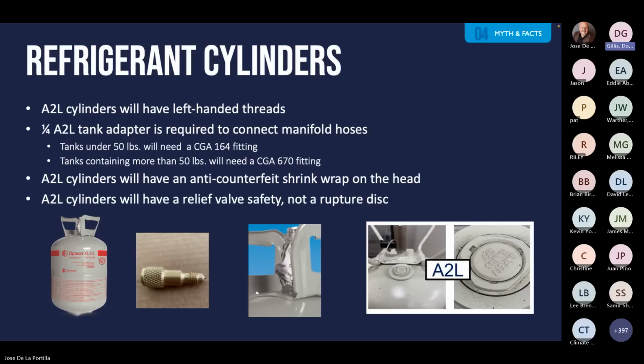So here's a thought that I have. When you put that shrink wrap around there, we here at Chemours, we get testing all the time. If refrigerant systems aren't running right, the last resort is let's test the refrigerant in it. Sometimes we find a refrigerant that's supposed to have three components in it has five, and one of them's like R125, which is half of 410A. That's a really high GWP.